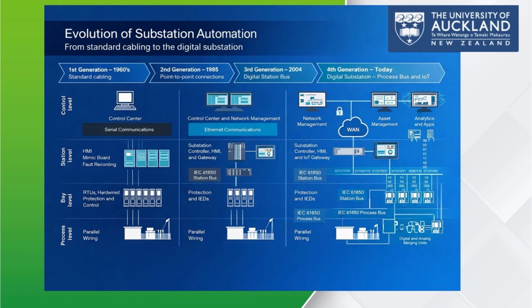And finally, today's fourth generation, the fully digital substation. This adds the IEC 61850 process bus with merging units that digitize CT and VT signals, and full IoT integration, right? So now sampled values and fast messages like GOOSE flow over the network. Protection, control, asset management, and analytics can all be done remotely and in real time. The result is less copper, faster protection, and a platform for predictive maintenance and advanced grid services.